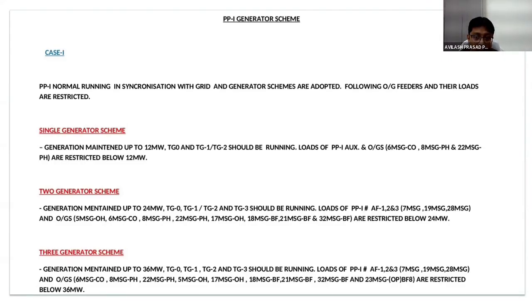Loads of PP1, that is auxiliary 1, 2, 3, and outgoing is 5 MSG OH, 6 MSG CO, 8 MSG PH, 22 MSG. These are the names of the different loads restricted below 24 megawatt. And for three generator schemes, generation mentioned up to 36 megawatt, TG0, 1, 2, 3 should be running.